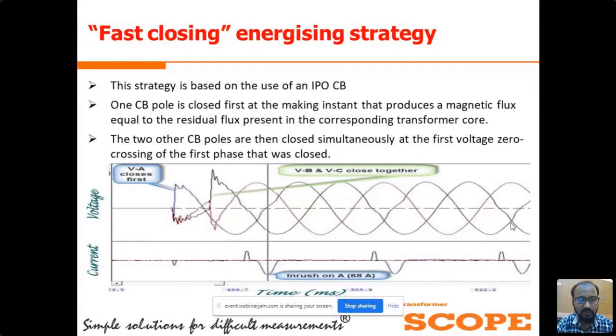For the power transformer application, as we have already discussed, there are basically two strategies for energizing the power transformer. One is the fast closing energizing strategy. This strategy is used only on individual pole operated circuit breakers. We are trying to close one pole at the voltage peak. We are trying to close first at the making instant that produces the magnetic flux equal to the residual flux present in the corresponding transformer core.